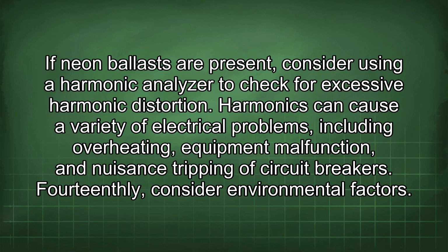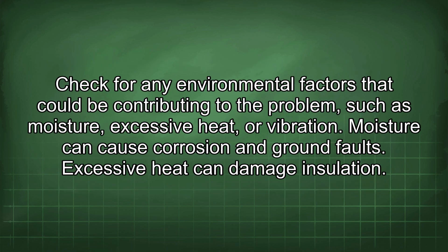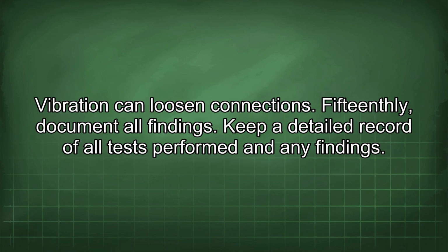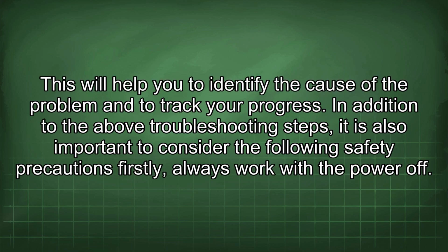14th, consider environmental factors. Check for any environmental factors that could be contributing to the problem, such as moisture, excessive heat, or vibration. Moisture can cause corrosion and ground faults. Excessive heat can damage insulation. Vibration can loosen connections. 15th, document all findings. Keep a detailed record of all tests performed and any findings. This will help you to identify the cause of the problem and to track your progress.